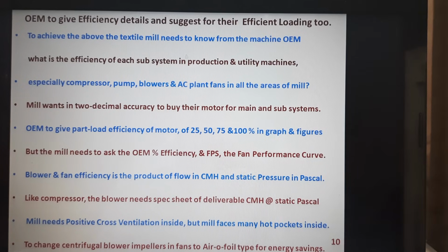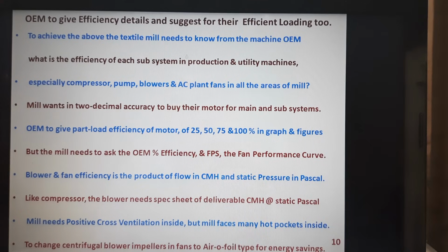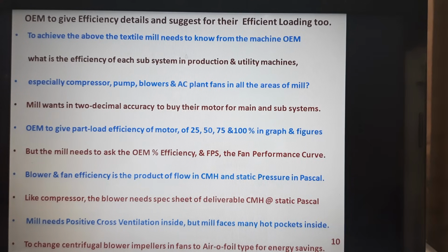See, if you take the case of a motor, the OEM needs to talk about the part load efficiency of the motor at 25, 50, 75 or 100% in graphs and figures, because the mill can operate a coarse count or a fine count, and each ring frame can operate from 30% or 20% to 80% also. In that case, the motor efficiency matters more, and that needs to be given by the motor OEM. Coming to the compressor OEM, he needs to give what CFM is deliverable at what compressed air header pressure, and what the kilowatt consumption is as a compressor package.